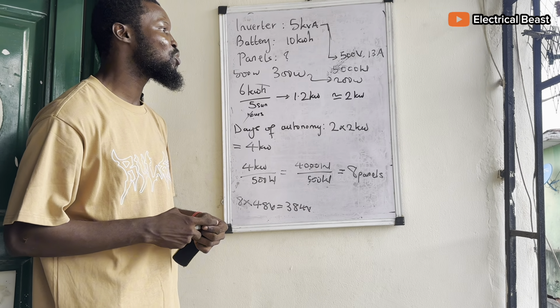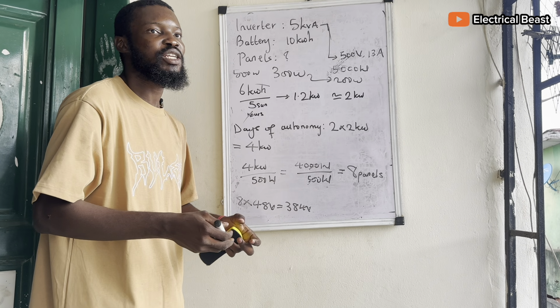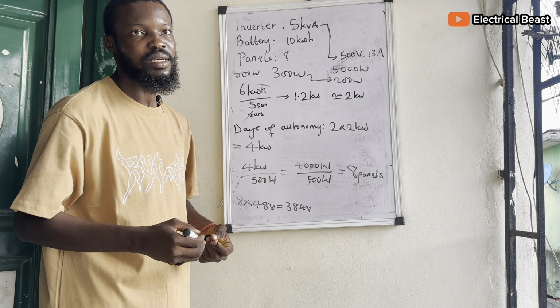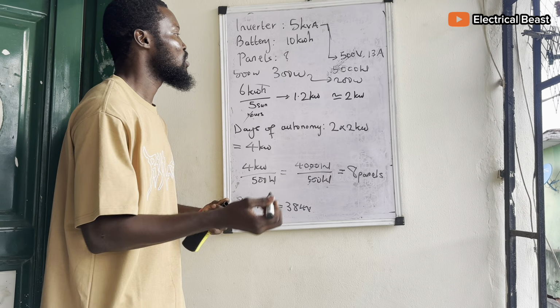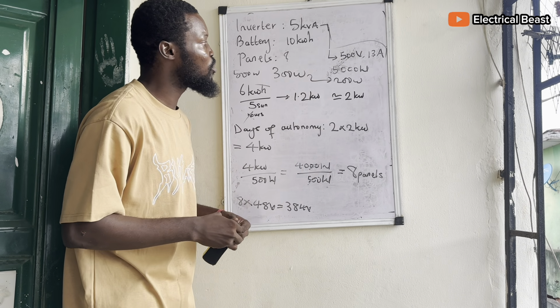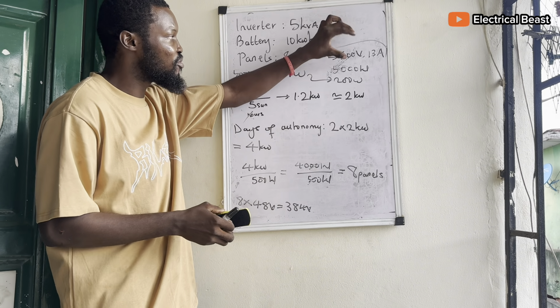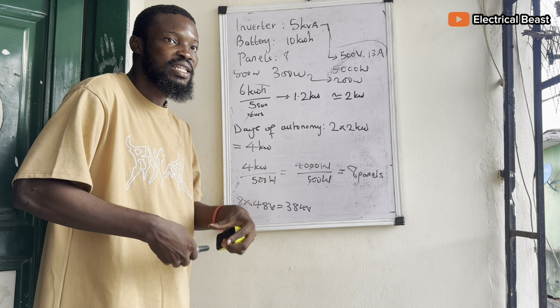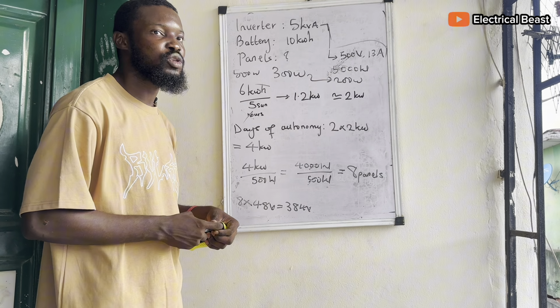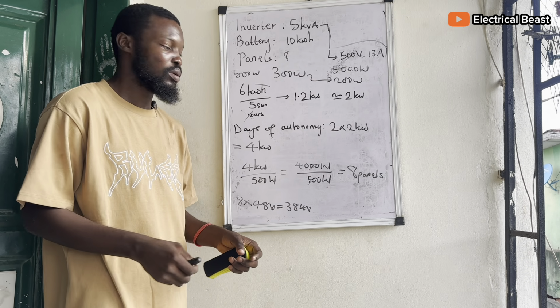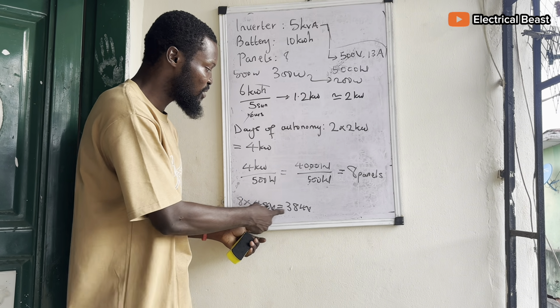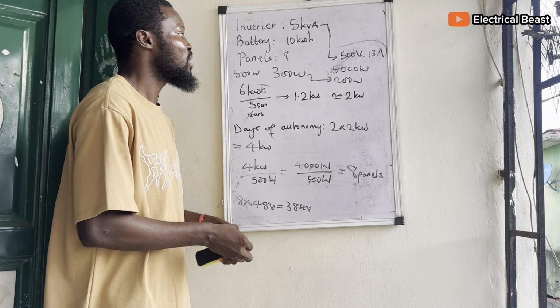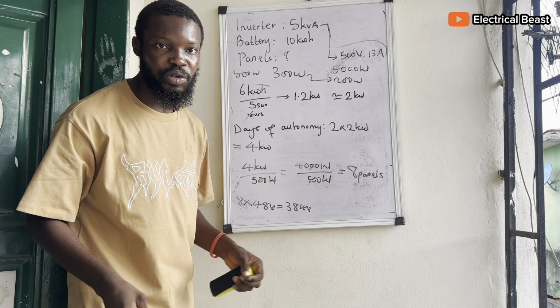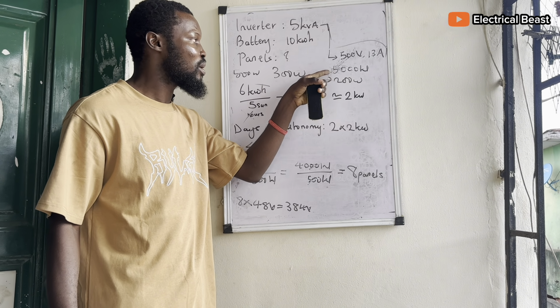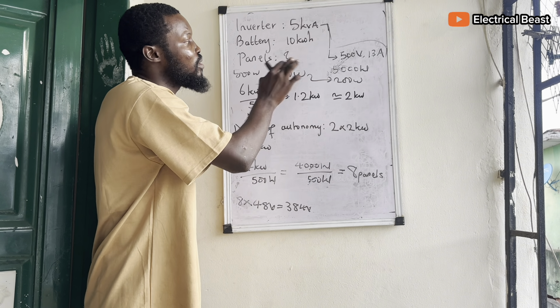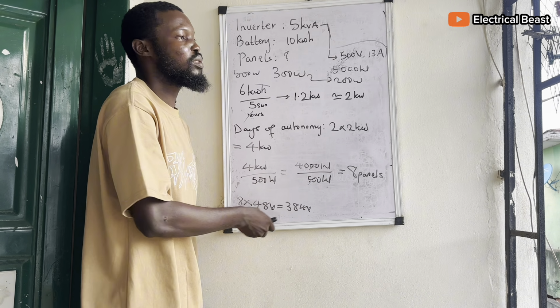Also, there's one thing you need to know. You can add panels to make sure the battery charging is faster, but you need to know that for hybrid inverters, there's a limit to the amount of panels you can add because they have a specification. For instance, the 5 kVA inverter, the specification is like 500 volts. You need to make sure the total panel voltage does not exceed 500 volts because you are connecting in series most times. So when you connect 8 panels in series, one panel is 48 volts. When you multiply 48 times 8, you have 384 volts. So you need to be very mindful. Make sure it is within the range. 13 amps, the current doesn't change when you connect in series. Then also, the maximum PV power that a hybrid inverter can accept for the 5 kVA is 5,000 watts. And so we're having 4,000 watts, 3,800 watts.